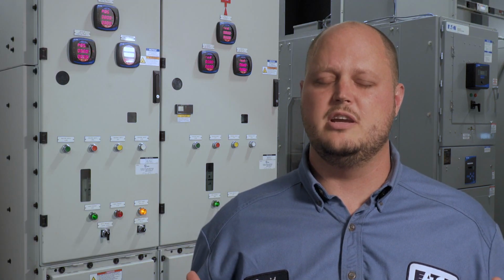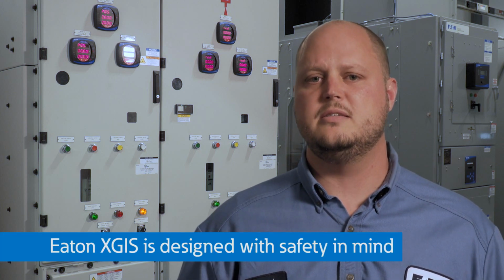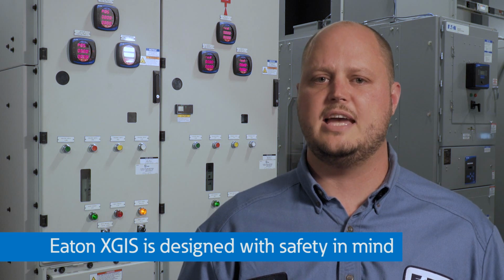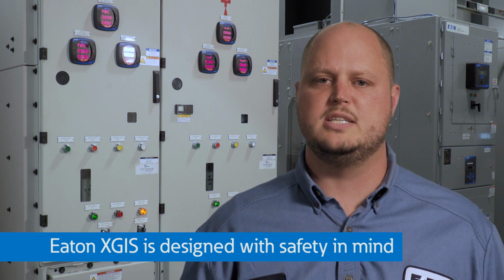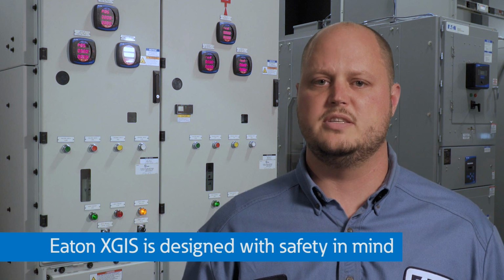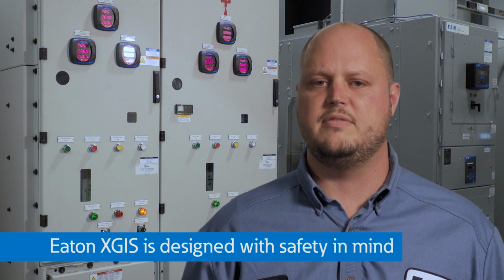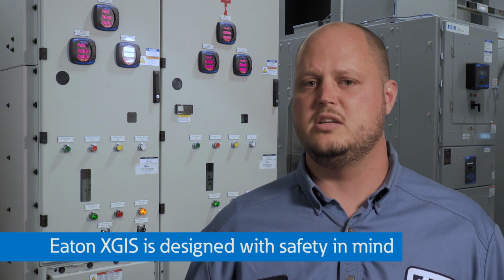In summary, prior to operating any gas-insulated switchgear, it is critically important to understand the available controls and safety features that are offered, including interlocking of the isolating and grounding operations. The Eaton Power Xpert xgis gas-insulated switchgear product was designed with a strong focus on the safety features to ensure operator safety, from the medium voltage utility and substation to the downstream feeder breakers.